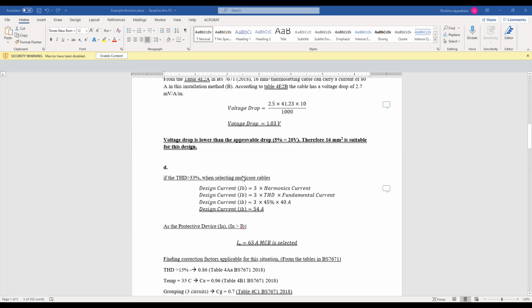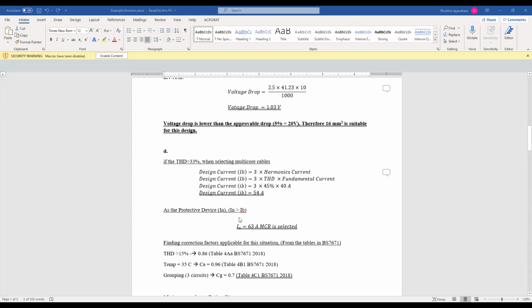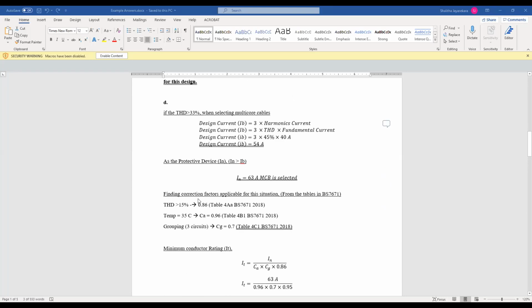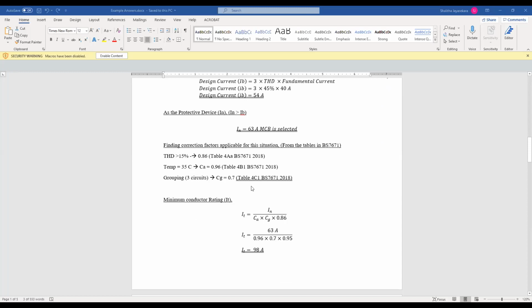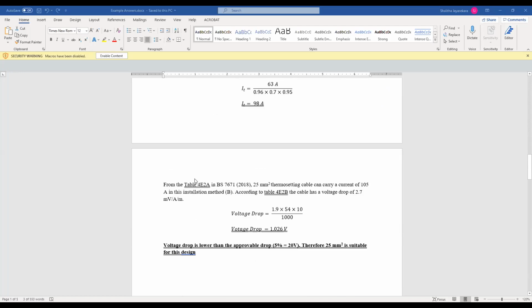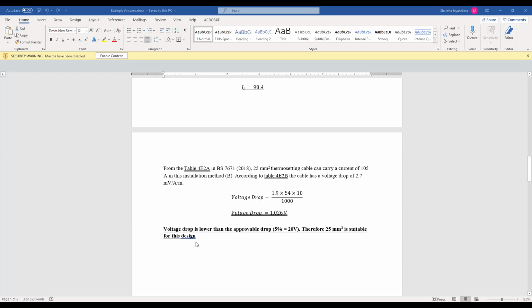So this is similar to the earlier. So the next part is similar. So you have to select MCB, then rating factors. In here also, yeah, actually this should be 45. In the table it was given that if your current is in between 33 and 45, you have to consider a 0.86 additional rating factor. So similar others will be similar, and you can easily get the current value and follow the same procedure and do the selection and check for the voltage drop and prove that this cable is sufficient for this design.